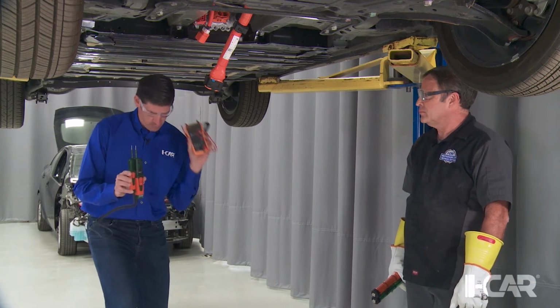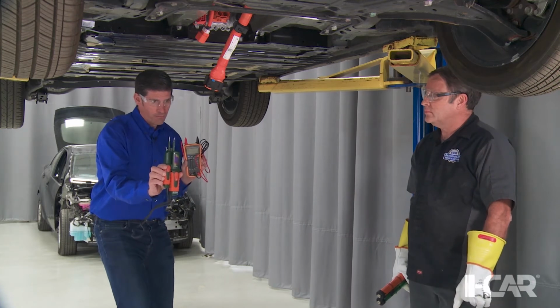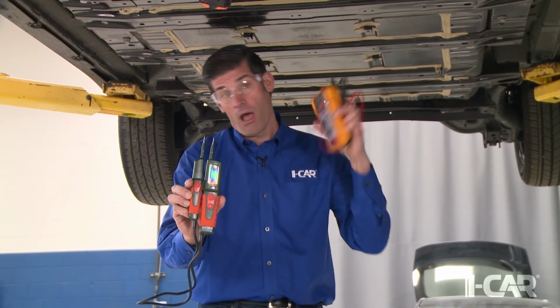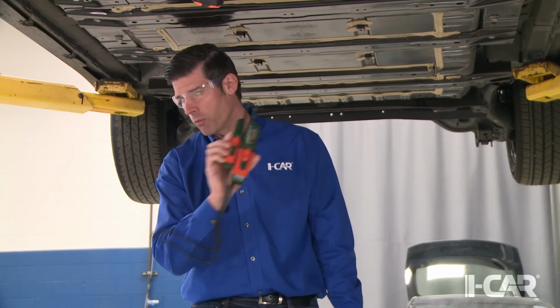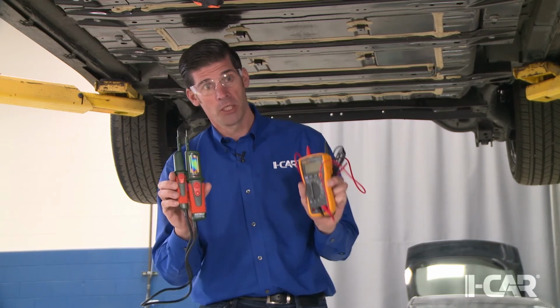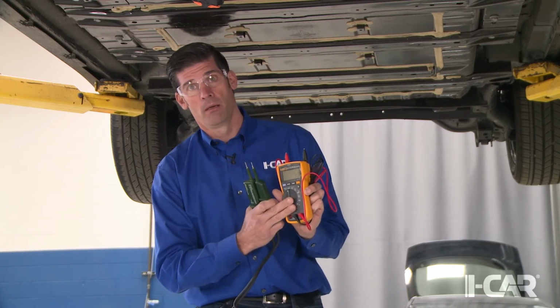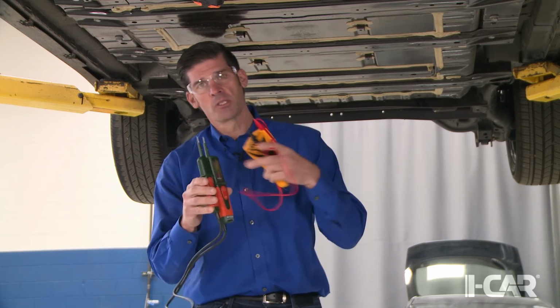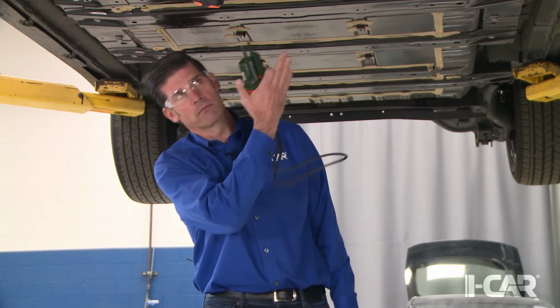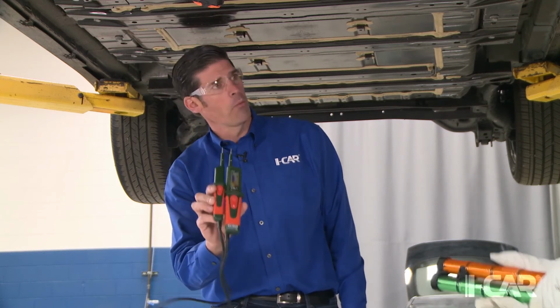So what is the difference between a multimeter and a 2-pole voltmeter? Nissan says use this one, but I'd like to use this other one. We're following the manufacturer procedures, but in this case, maybe you trust me. The reason I like to use this is that it's a voltmeter that measures only voltage. It's not dependent on an external battery like this one, where I need a battery to operate it. So when the battery here would not work and I measure a power source like the 400 volt battery, it would still show me 400 volts.